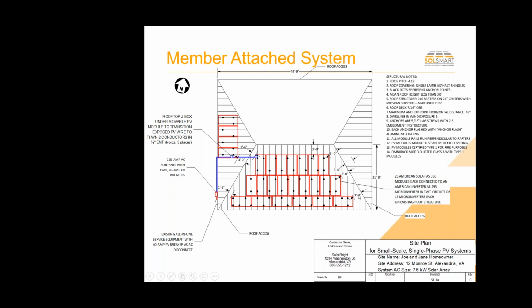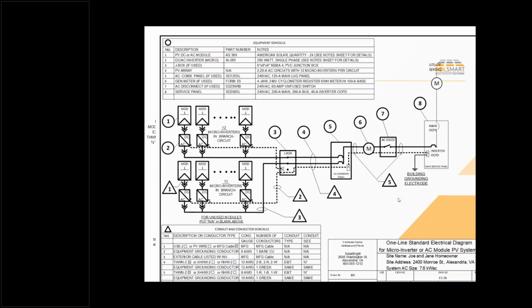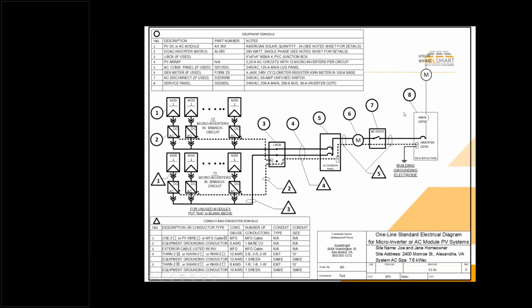So every single rafter in this block here is attached to, and we can see from that system, it's a different layout. We've got some south-facing panels, we've got some west-facing panels, but since they're all independent of one another, they're all running together into 2 separate circuits. So it says we've got 26 modules, we've got 26 inverters, and we've got 2 circuits of 15 microinverters each. Well, no, we're not going to have 15. We're going to have 13 microinverters each. So that's a checker trap there. Should say 13.